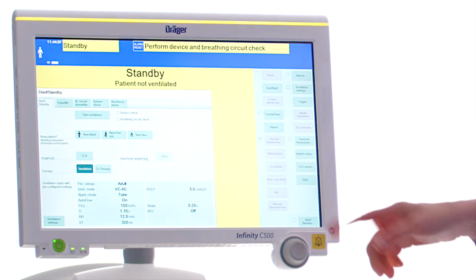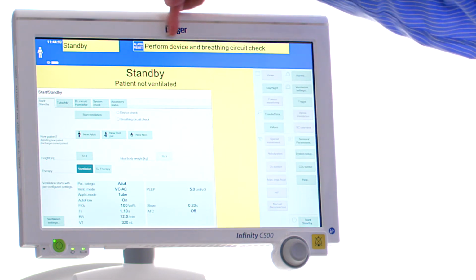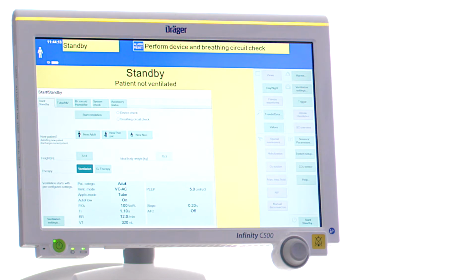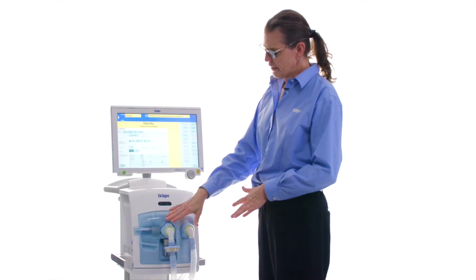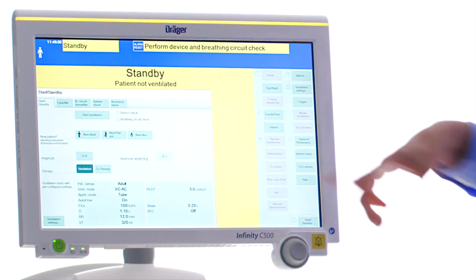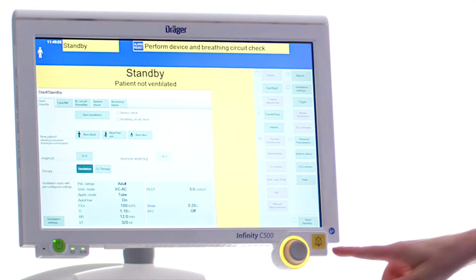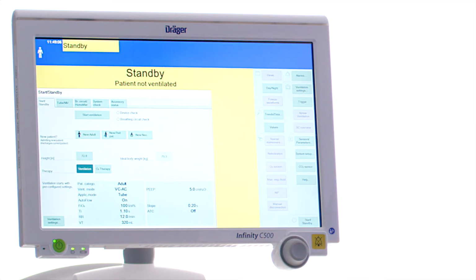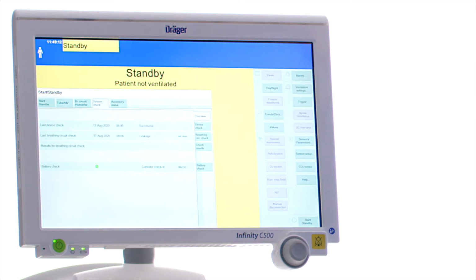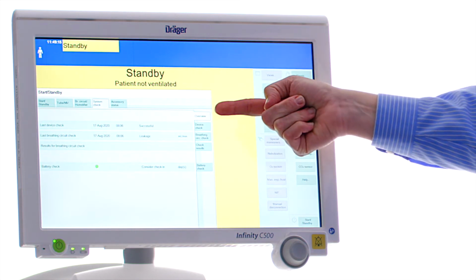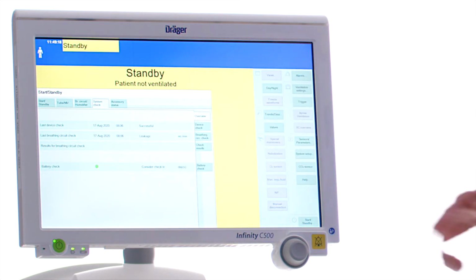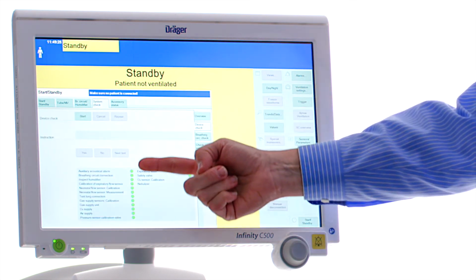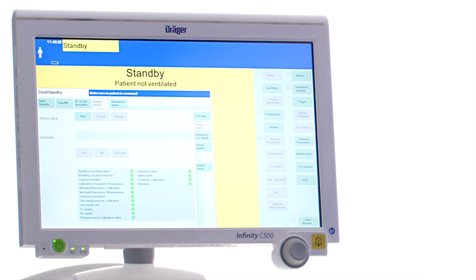Once the ventilator has gone to the standby screen, the ventilator will also remind you to perform a device check and breathing circuit check. This is done when the ventilator is cleaned and reset up. This can be cleared by touching the alarm reset button right next to the message and confirm by pressing the rotary knob. To confirm that the device check was done successfully, touch the System Check tab on the top of the window. You'll see an overview that tells you the last device check that was done, and it will show you the status of that check. By touching Device Check, you can confirm that every component of the device check was done, and the green button will indicate that each one was successful.